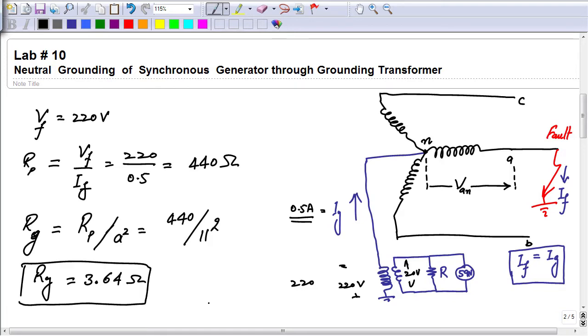Now I am going to explain it again. If we insert 3.64 ohm here at this location, that is the secondary side of this grounding transformer, which is rated at 20 volt, then this value 3.64 will appear as 440 ohm on the primary side of this transformer, which is actually the connection between neutral and ground. In case of a line to ground fault at the terminal A, due to this high 440 ohm resistance in this path, the current that will flow will be 0.5 ampere. So this is how we can calculate the value of resistance to be inserted on the secondary side of this grounding transformer, which will limit the current according to our required value.